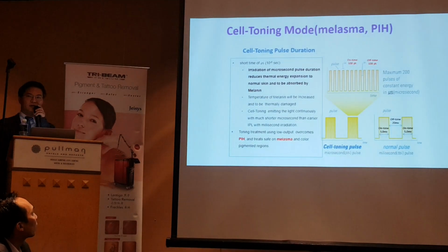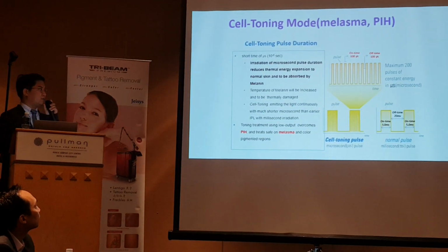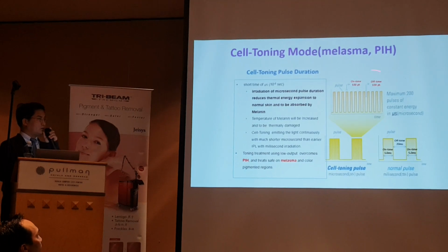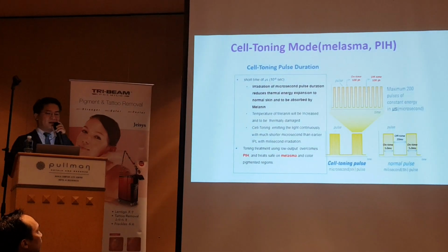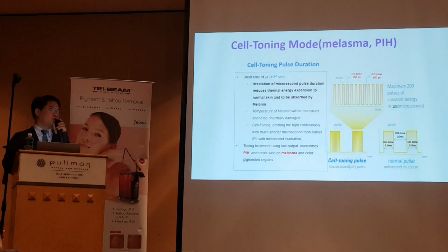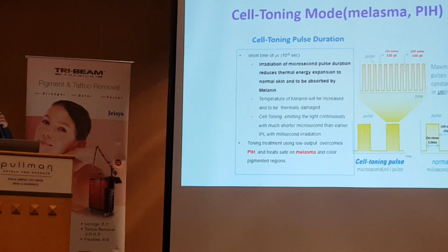Cell-Toning mode is for melasma and PIH. The on time is 100 microseconds, and off time is 100 microseconds, a very short pulse duration.